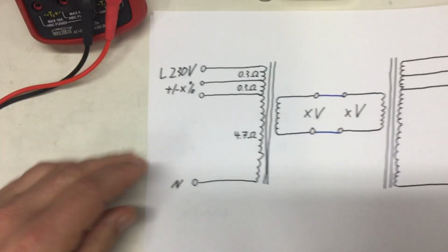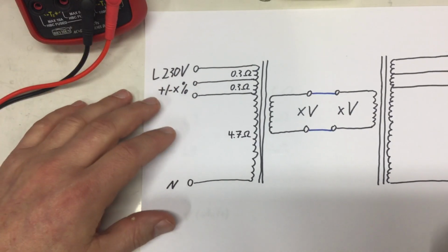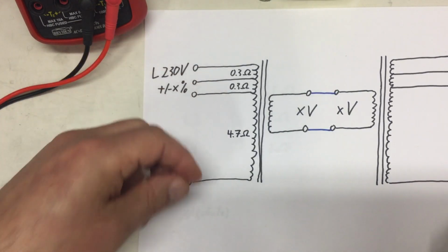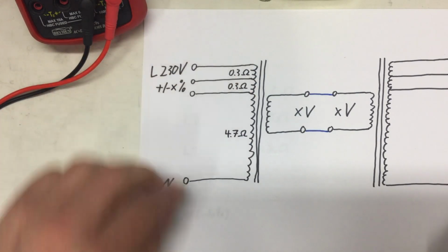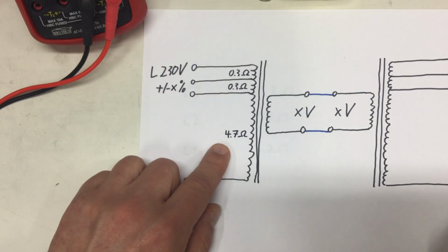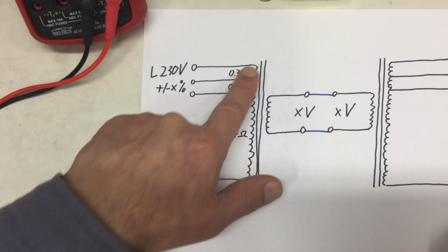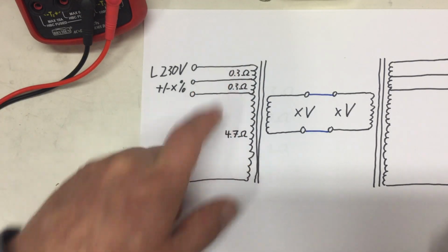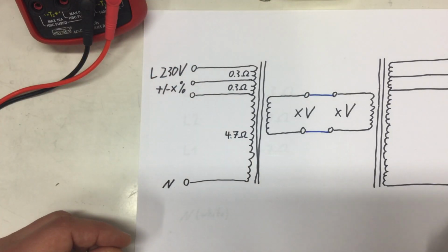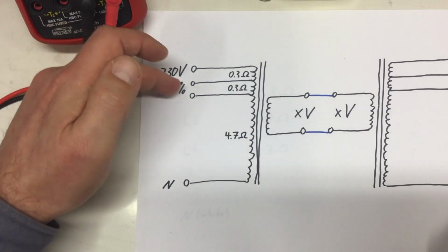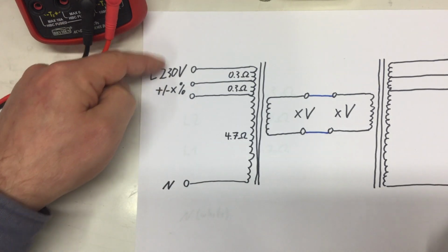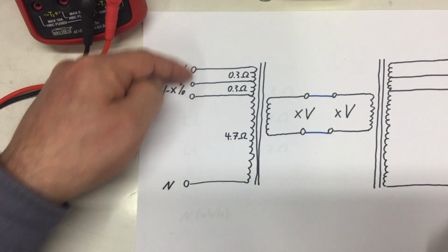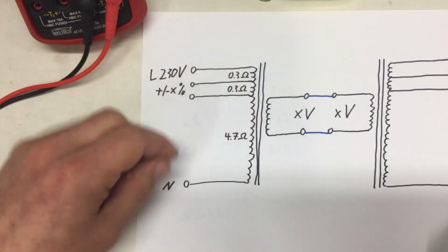So just the resistance of our primary windings looks something like 4.7 ohms, with the smaller taps at about 0.3 ohms difference. You could do some calculations now for how many plus or minus X% from 230 volts this represents, but we'll measure it anyway later.